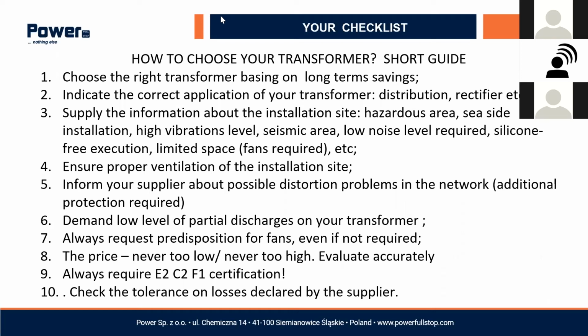Important point: silicone-free execution. For example, this week we are supplying some transformers to Germany, to Daimler, and it's quite a big, huge order. We have more than 10 units, 2000 kVA, in silicone-free execution. Silicone is used a lot in cast resin transformers, so if you have this information, be sure to give it to your supplier, because some components must be exchanged, replaced with a different material.